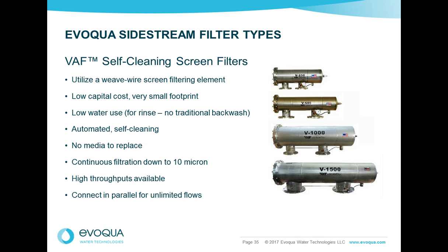The other one I'd like to touch on is the VAF self-cleaning screen filter. Now, these filters use a weave wire filter element. They're inexpensive, low capital cost, they're compact, and they can handle very high flows. You can connect them up in parallel, and they don't need much maintenance. I've used these quite a bit over the years.